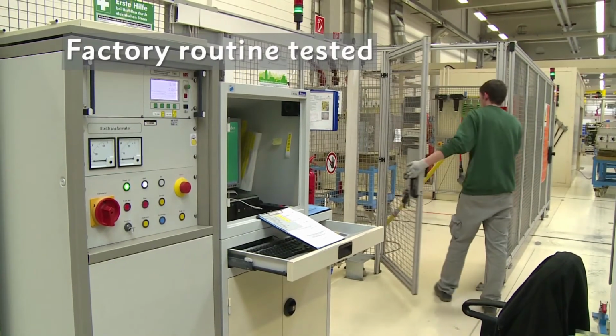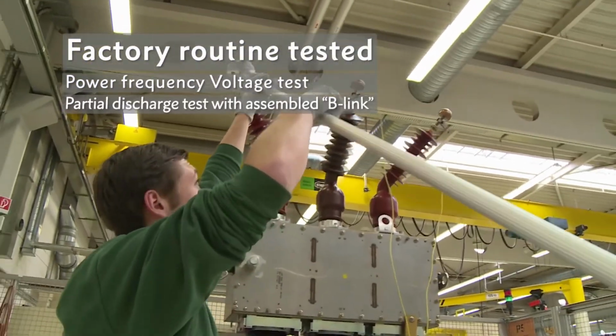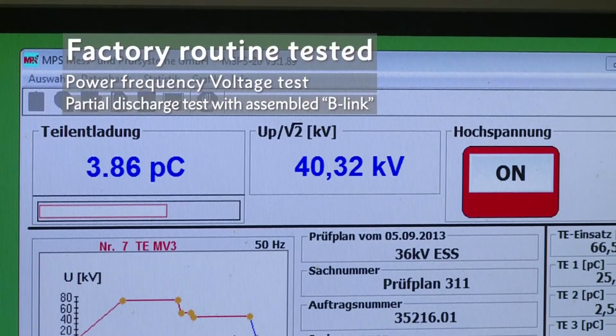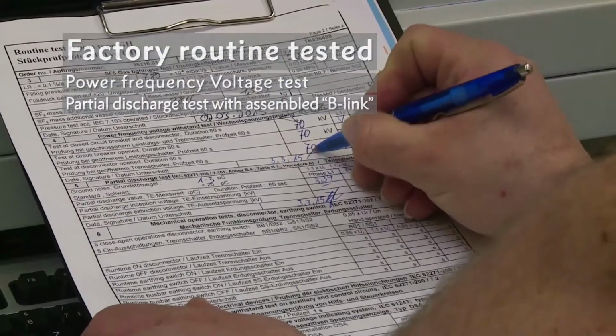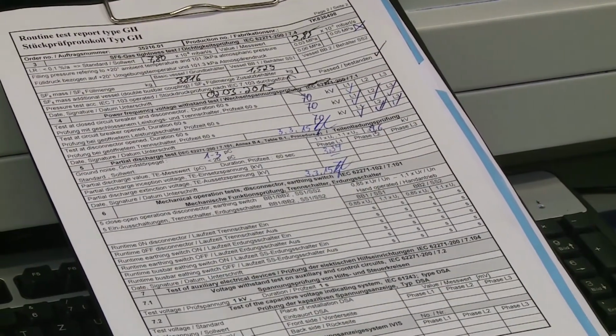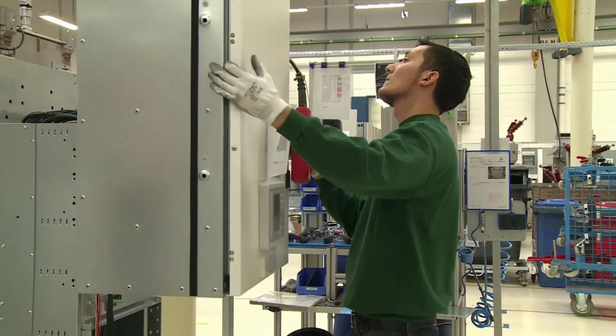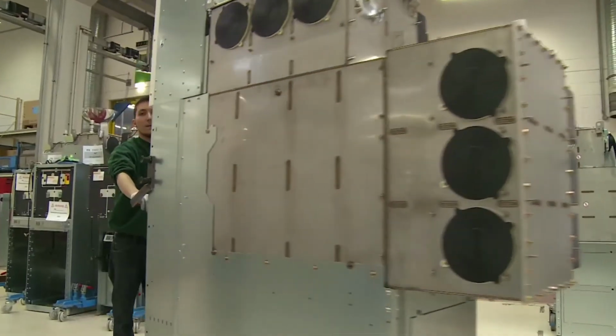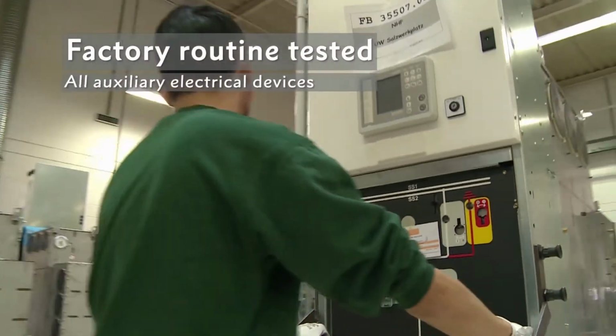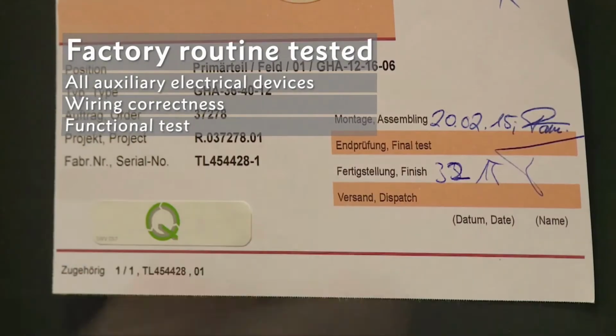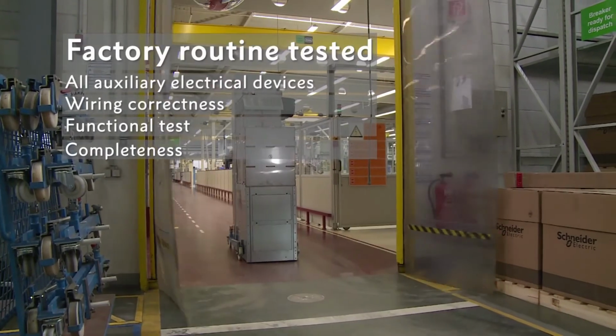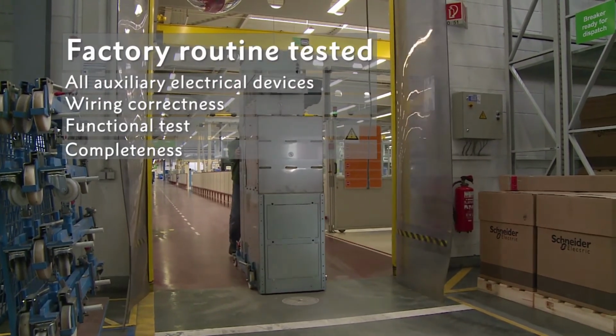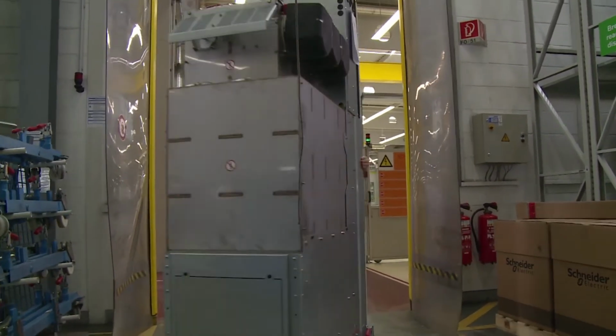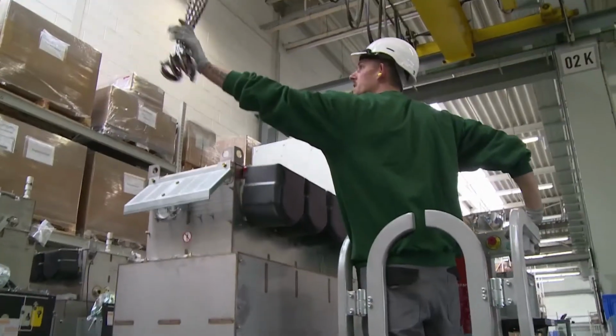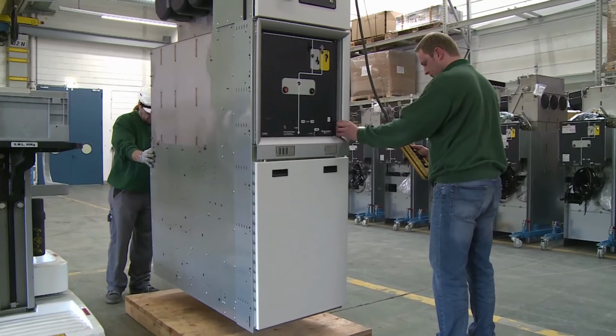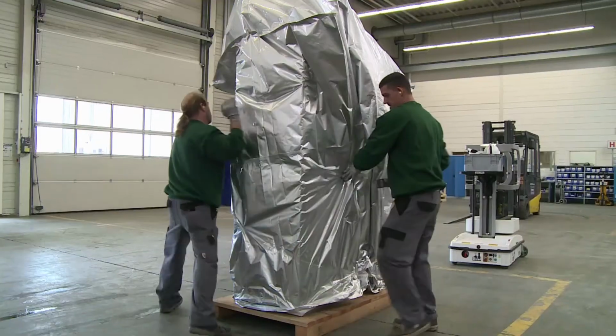The next important routine tests are the power frequency voltage test and the partial discharge test. For GHA, these are performed with a fully assembled busbar link in the factory. The signature of an expert confirms that every routine test has been carried out successfully. The low-voltage control cabinet is now installed in the medium-voltage panel, before being moved to the routine test area for all auxiliary electrical devices. The last routine checks are performed in the plant finishing area to ensure that all components are complete and will function correctly when your GHA is installed. The panels are finally moved to the dispatch area, where they are prepared for their journey. The utmost care is taken when packing and preparing for shipping, regardless of whether equipment is transported by land, sea, or air.